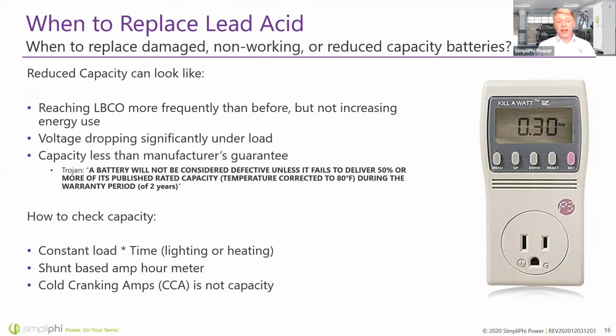You can also check your capacity, and Trojan says that their capacity guarantee is essentially if the battery fails to deliver half of its published capacity during the first 2 years. And just for comparison, our warranty is 80% within 10 years. So you can check capacity in several ways. One of them, you can just use a constant load and a known amount of time. So constant load would be something like lighting or heating. Maybe you have a resistive heater like a dish heater and you want to put it on full blast. That would be a constant known load.